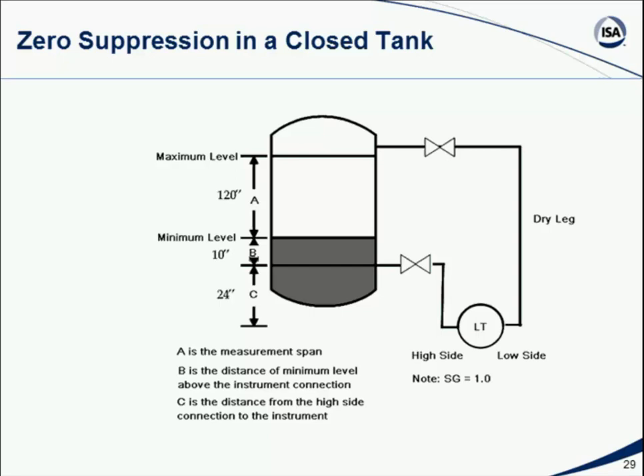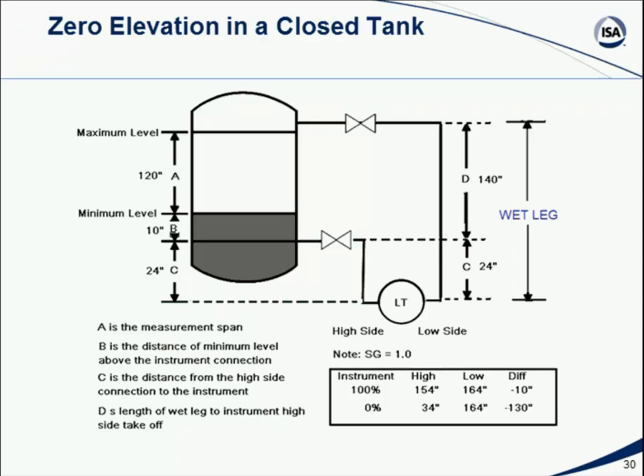So again, this arrangement corrects for the pressure in the vessel, but we still have the problem of zero suppression. So even though we've corrected for the effects of pressure, just like we correct for the effects of atmospheric pressure, we still have to zero correct. We still have a transmitter that is tapped in at 10 inches below the minimum level of the fluid in the tank and located 24 inches below that tap. So in other words, that fluid in the high side leg will always be a minimum of 34 inches of fluid. So we've still got the problem of zero suppression, but we've just corrected with a dry leg connection to the top of the tank. We've corrected for the problem of the pressure in the tank. And that sounds great, but there's another problem, and that is we refer to that leg on the right-hand side as a dry leg, and that's great.